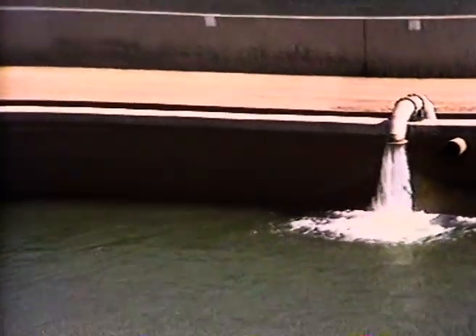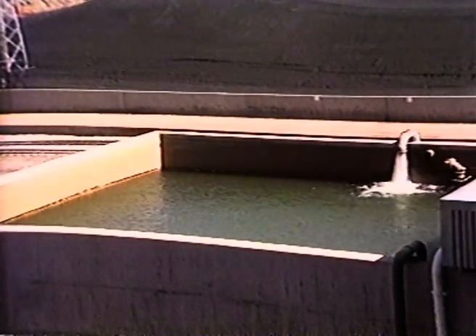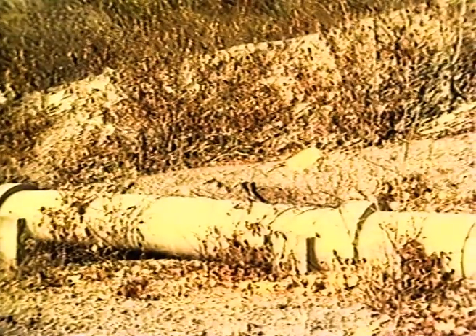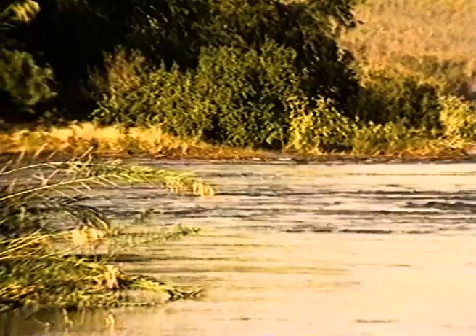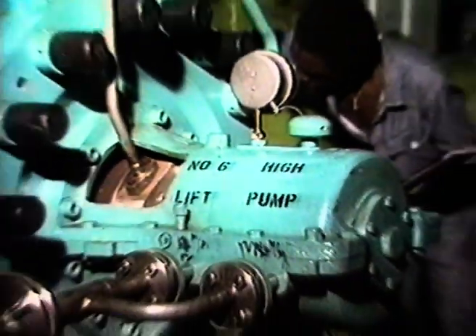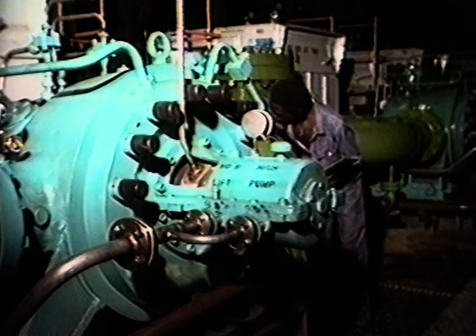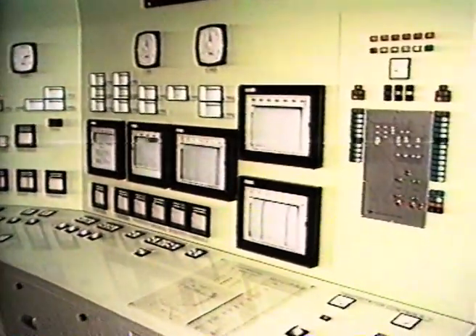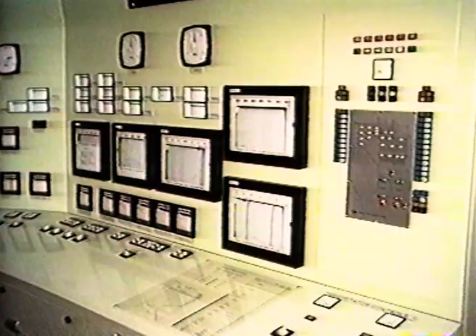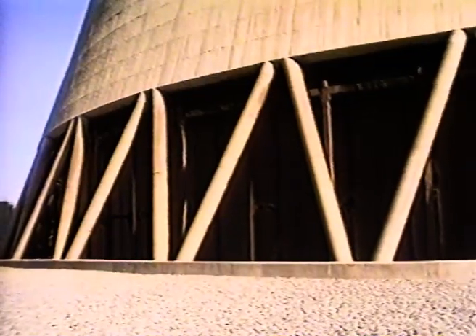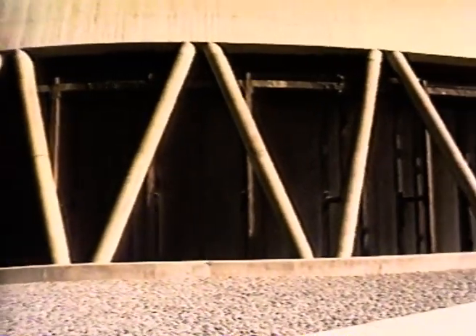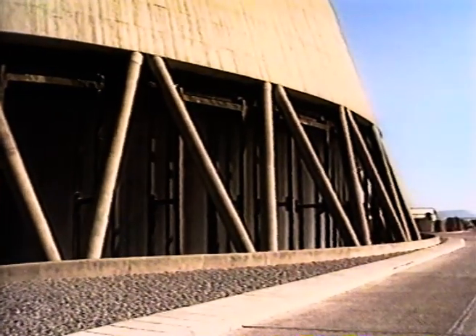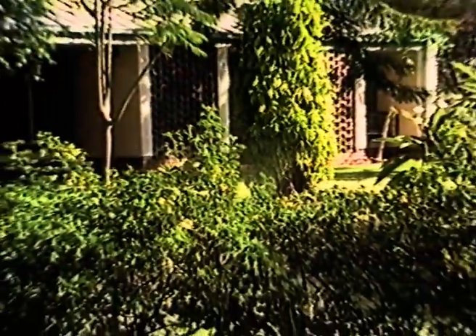The plant's water requirement is pumped along a 43-kilometer long pipeline from the Zambezi River at a point near the Deka fishing community. Both high and low lift pumps are utilized, and these can be remotely operated from the power station. 77,280 cubic meters of raw water per day is needed by the power station when running at full capacity, and in addition to meeting this requirement, Hwange's filtration systems can produce up to 40 cubic meters of clean drinking water per hour for the residential estates and domestic supply of the power station.